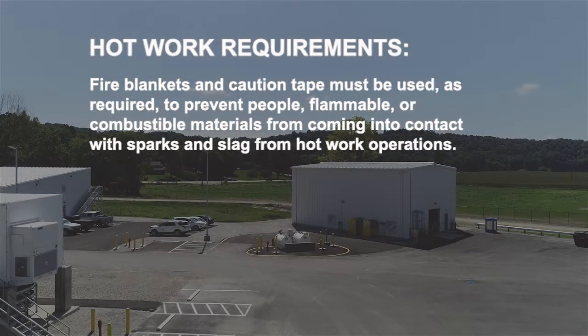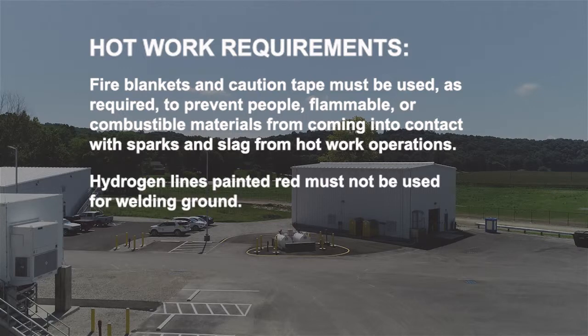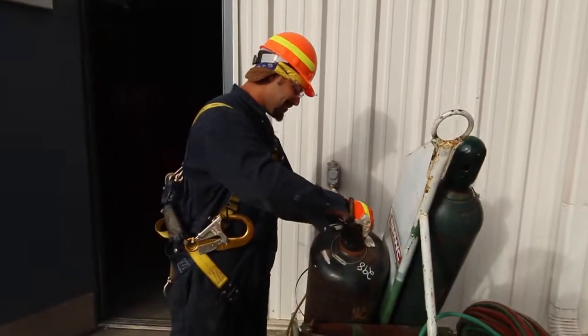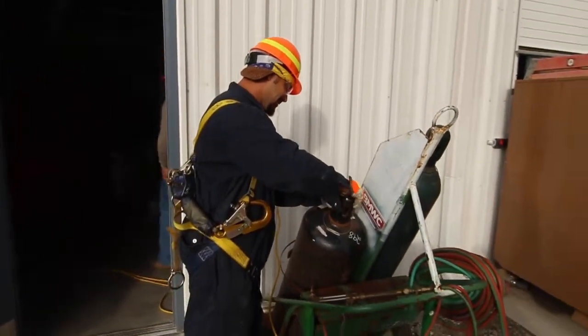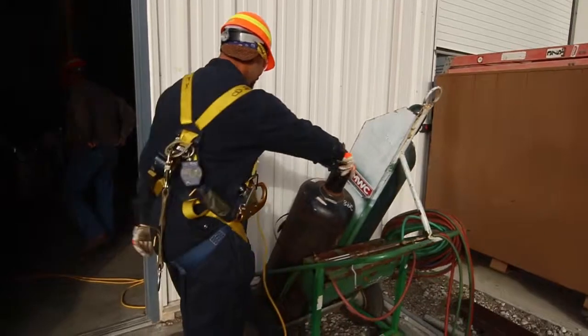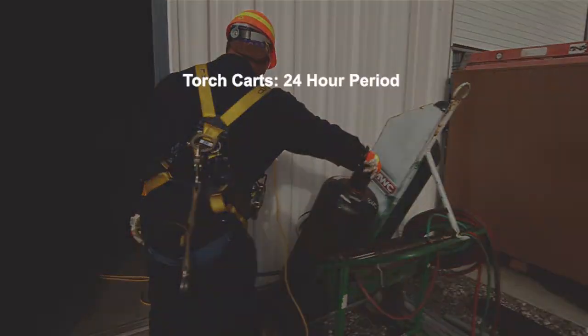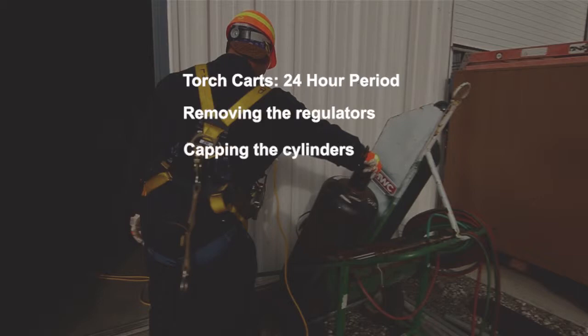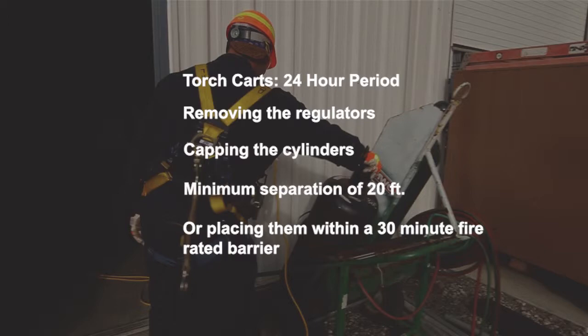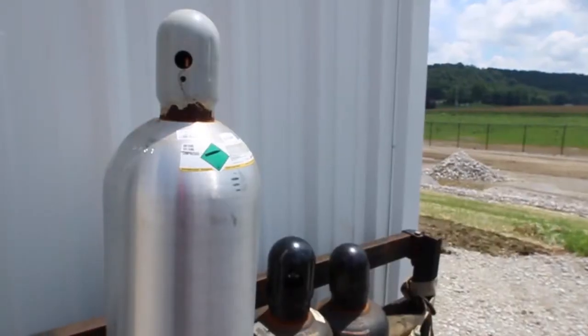Fire blankets and caution tape must be used as required to prevent people, flammable or combustible materials from coming into contact with sparks and slag from hot work operations. Hydrogen lines painted red must not be used for welding ground. Torch carts. When transporting bottles or carts, the regulators must be removed and cylinders capped. If torch carts are not going to be used within a 24-hour period, they must be stored properly by removing the regulators, capping the cylinders, and either separating the bottles by at least 20 feet or placing them within a 30-minute fire-rated barrier.